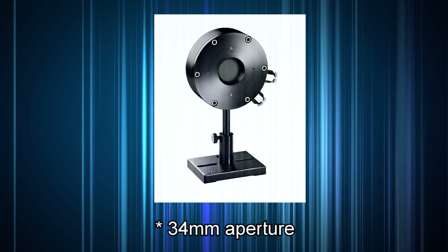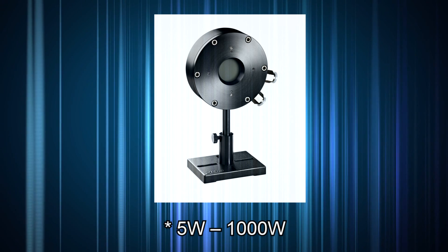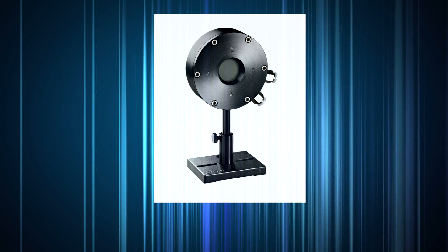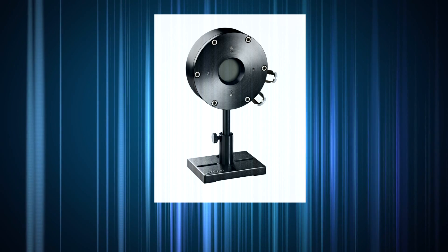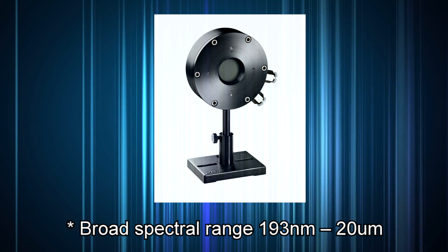that's the meaning of the 34 in its name, and a wide dynamic range, measuring powers from 5 watts to 1000 watts, as well as single-shot energy from 400 millijoules to 300 joules. The broadband absorber can measure over a spectral range from 193 nanometers to 20 micrometers.